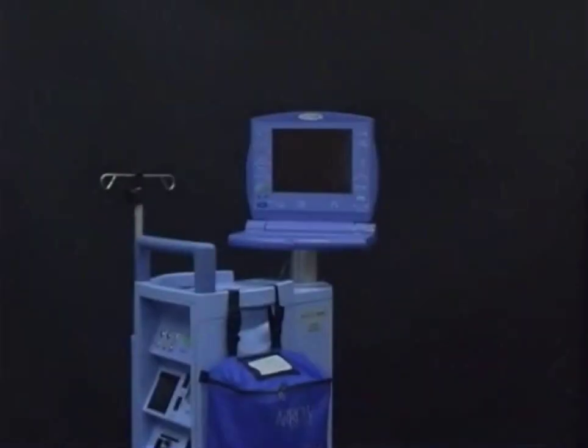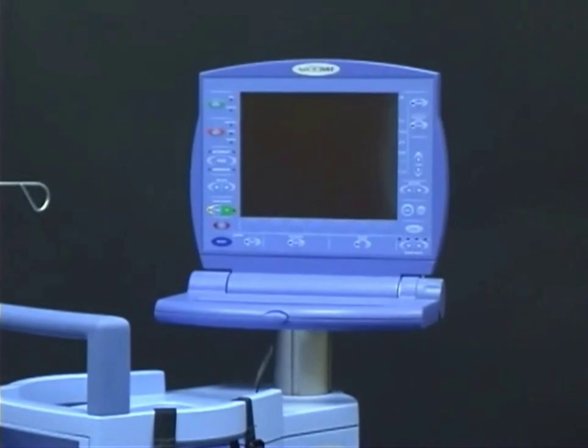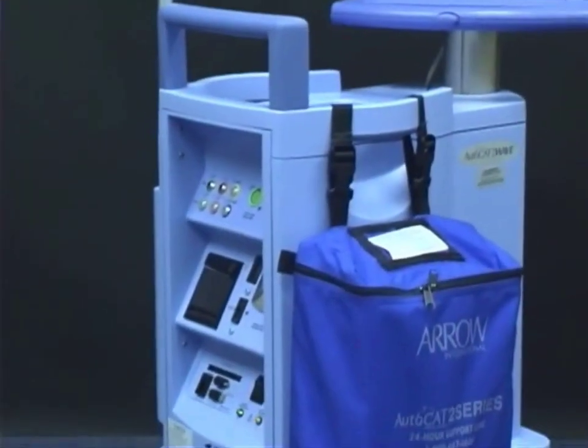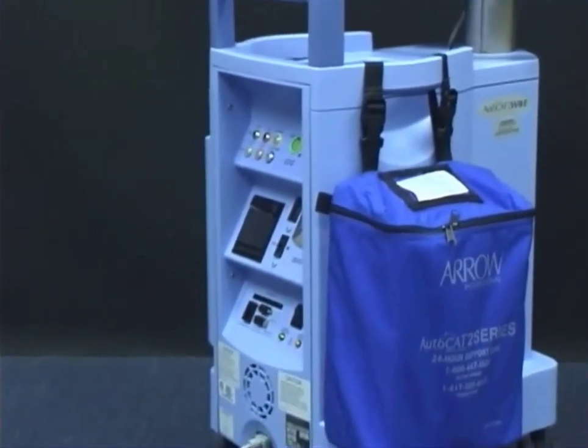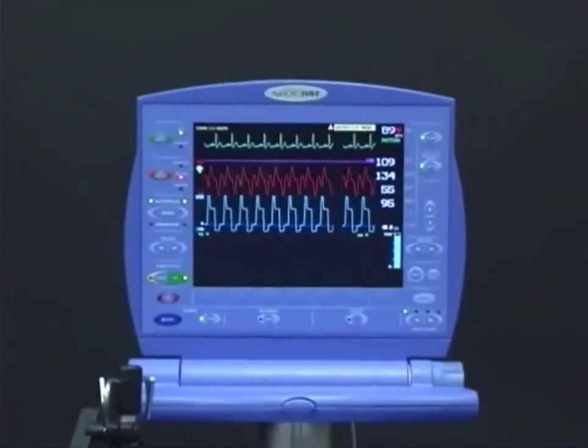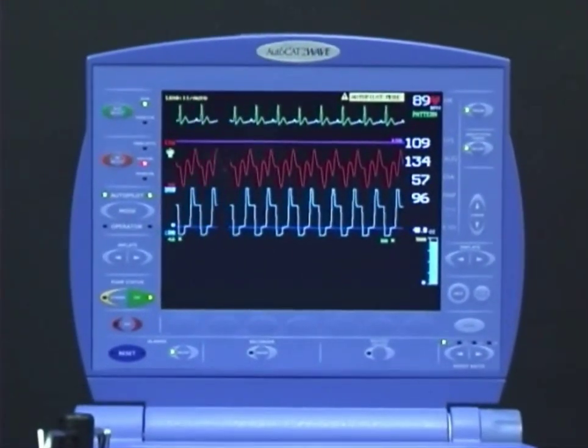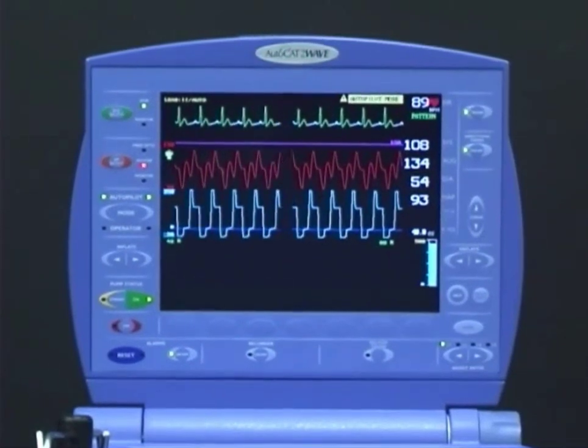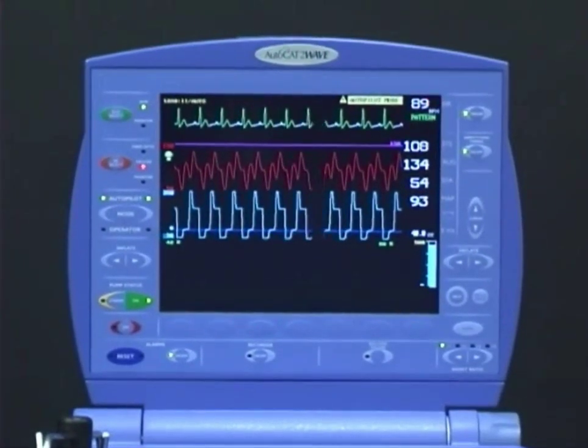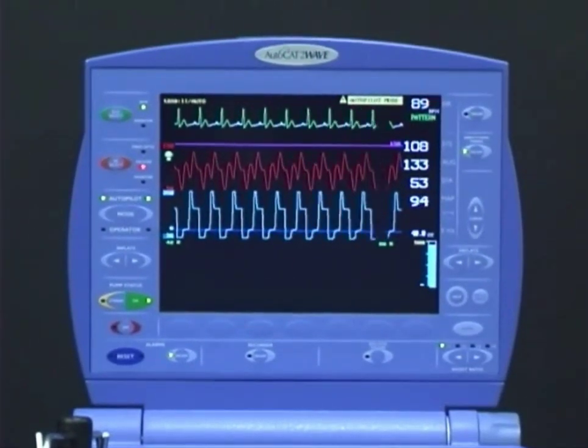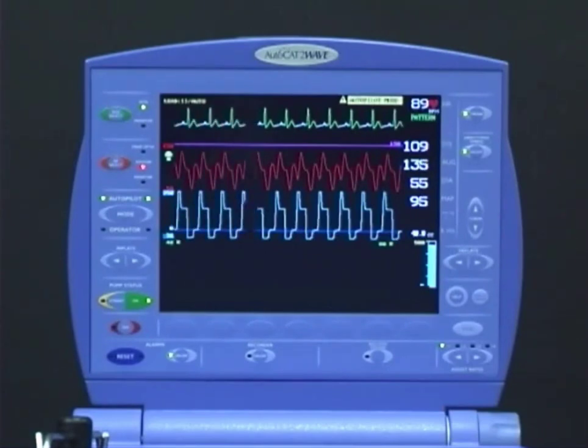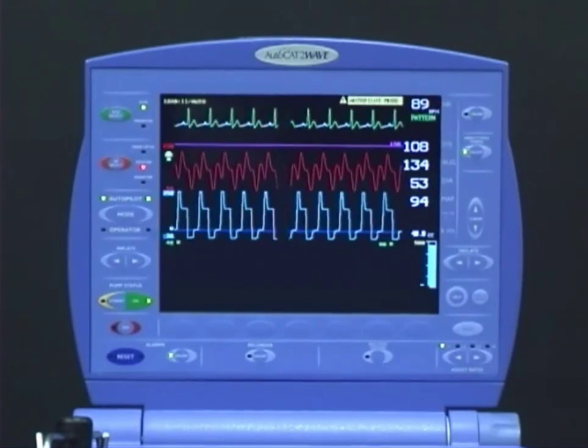The AutoCAT 2 Series is made up of two components: a control module and a pneumatic drive unit. The control module contains the function keys and the display monitor. The display is a high-resolution, color LCD screen. The screen displays ECG, arterial pressure, and a calibrated balloon pressure waveform.